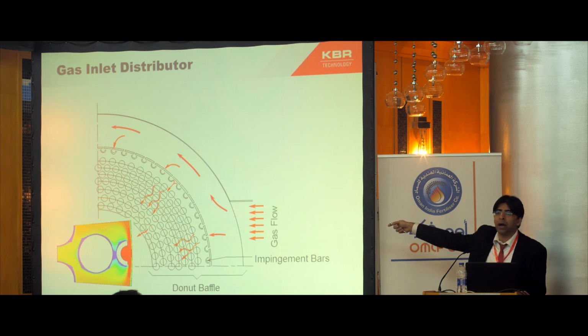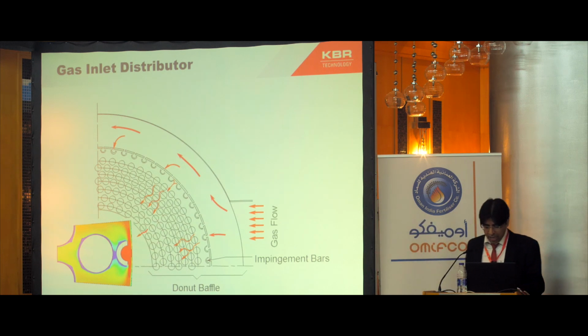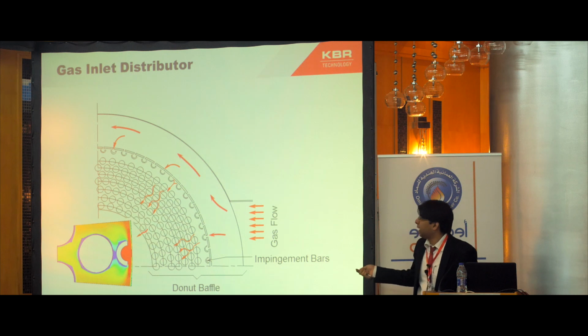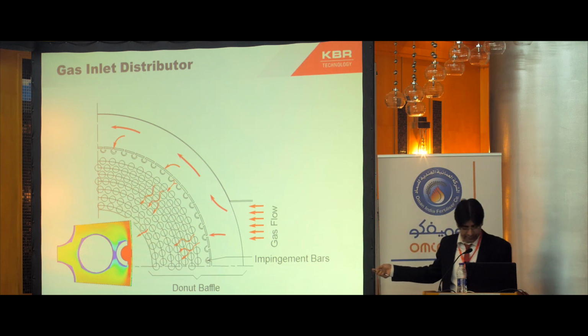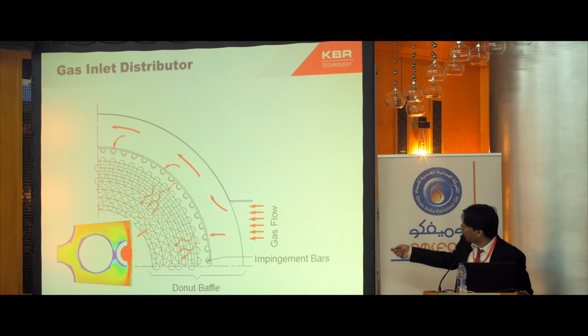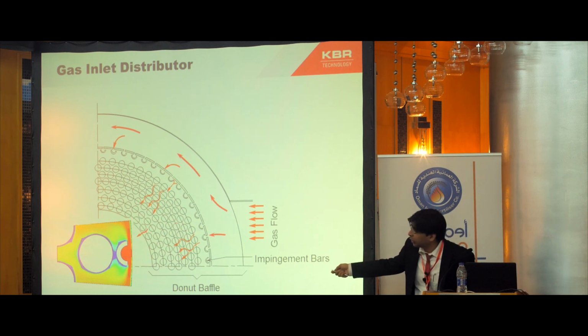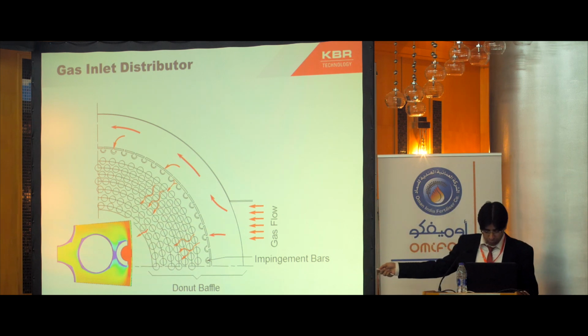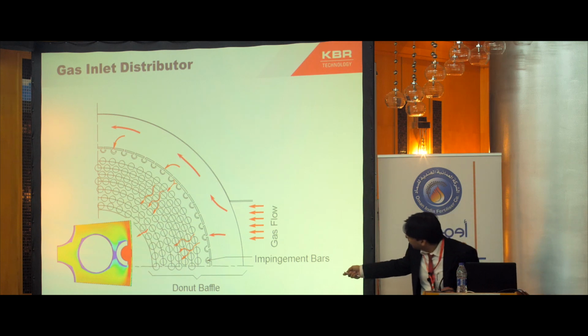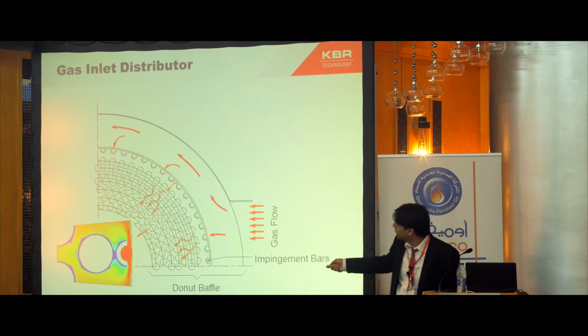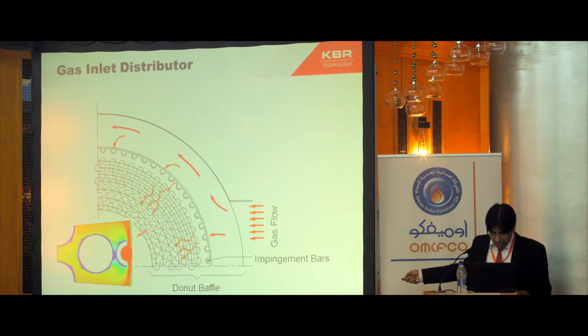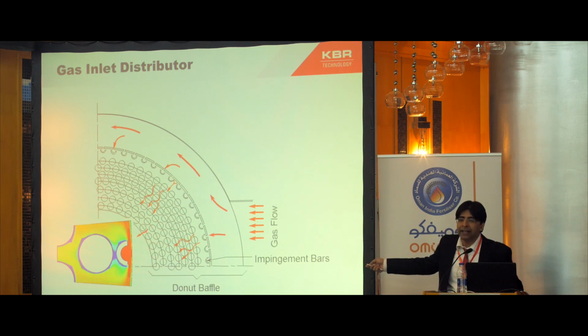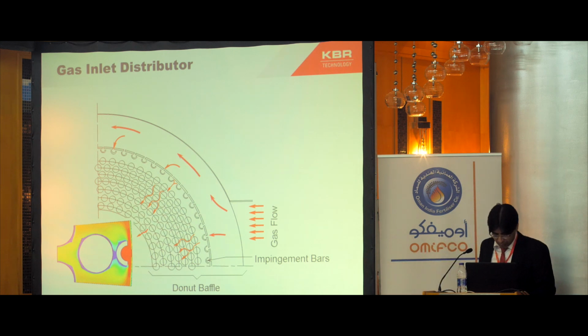You'll see the impingement bars to take care of the temperatures. The gas coming in is at around 900 to 1000 degrees C. In order to avoid direct impingement of the gas flow on the tubes, which can result in failure of the tubes, these impact bars are placed. They also help in guiding the flow through the tubes on the shell side. So these are the impact bars.